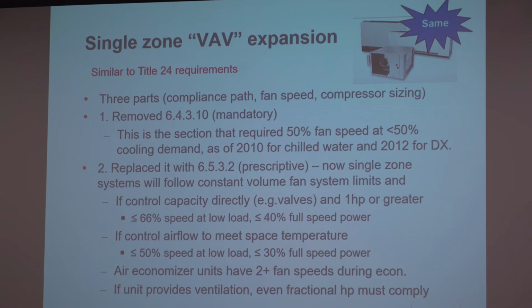It's not truly single zone VAV because it really talks about how we do our compressor staging and how we do our fan speed control. So in the original incarnation of single zone VAV, we basically said that we wanted you to be able to turn down your fan speed, especially during economizer mode. So the second to last bullet here, if you have an economizer mode, we want you to have at least 2 fan speeds during that mode. And then depending on how you control the system, we want you to be able to have lower fan speed.